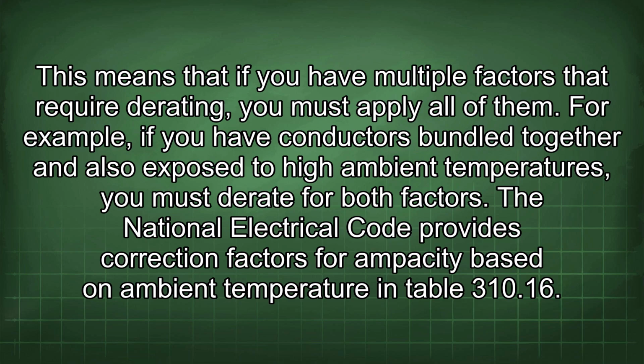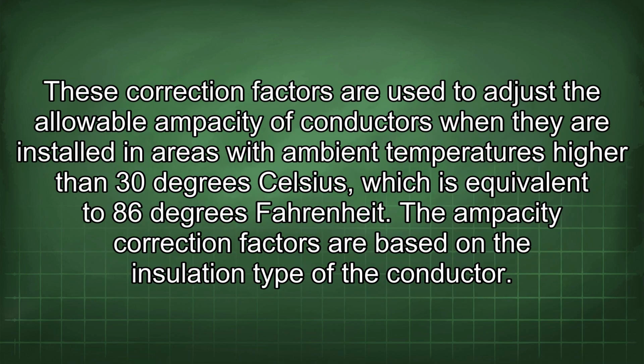For example, if you have conductors bundled together and also exposed to high ambient temperatures, you must derate for both factors. The National Electrical Code provides correction factors for ampacity based on ambient temperature in Table 310.16. These correction factors are used to adjust the allowable ampacity of conductors when they are installed in areas with ambient temperatures higher than 30 degrees Celsius, which is equivalent to 86 degrees Fahrenheit.